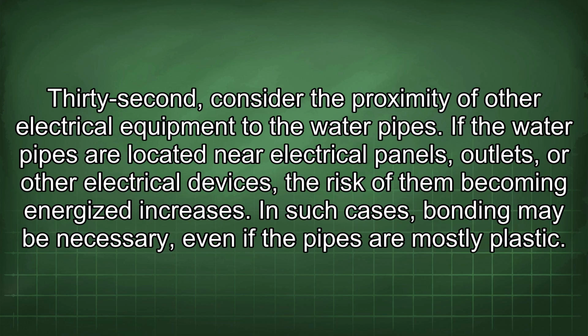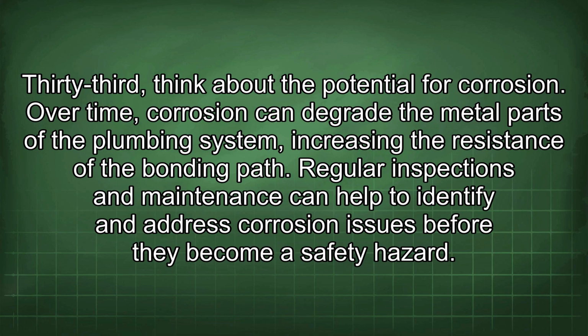32nd, consider the proximity of other electrical equipment to the water pipes. If the water pipes are located near electrical panels, outlets, or other electrical devices, the risk of them becoming energized increases. In such cases, bonding may be necessary even if the pipes are mostly plastic. 33rd, think about the potential for corrosion. Over time, corrosion can degrade the metal parts of the plumbing system, increasing the resistance of the bonding path. Regular inspections and maintenance can help to identify and address corrosion issues before they become a safety hazard.